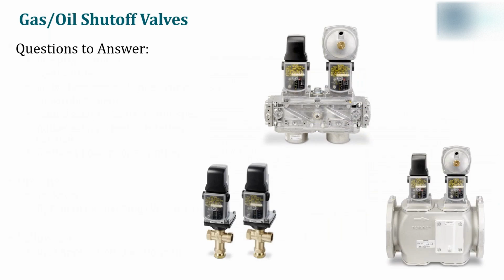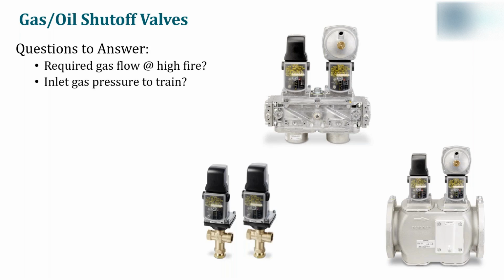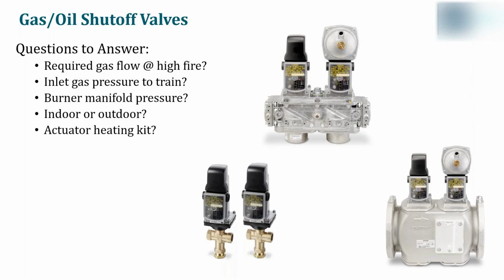Next, we're going to cover the gas oil shutoff valves. Now, the questions we need to answer here are: what is the required gas flow at high fire? What is the inlet pressure, or gas pressure, sorry, to the train? What is the burner manifold pressure? Is it an indoor or outdoor application? Does it require an actuator heating kit? This would be primarily if the temperatures are sub-zero. And finally, are you looking for a complete train or just loose parts?